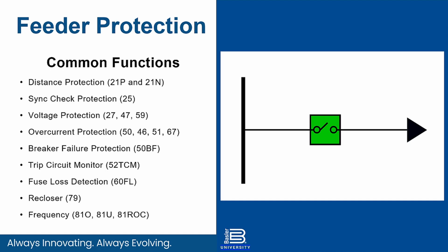From a protective relay standpoint, one of the core points that protective relays exist is in feeder protection. So feeder protection historically has often existed with overcurrent protection. Those are 50 and 51 elements. If you wish to have directionality or negative sequence or other variation algorithms on that, you would call them 46 functions, 67s, or a variety of other things. Additionally, in lots of places you're going to have things like voltage protection, such as over or under voltage, over or under frequency, or even rate of change frequency. Common in utility systems is a reclosing function on those feeder protections.